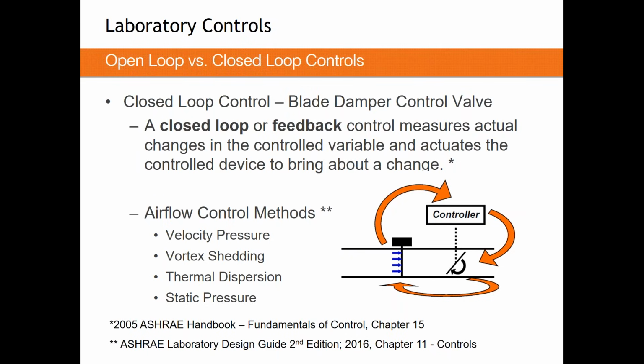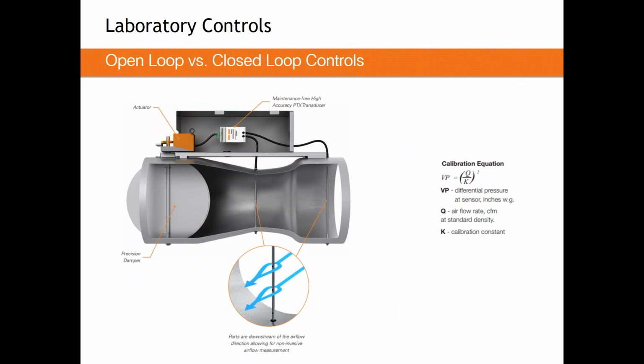The other way you can do it is measuring static pressure. I'll show an image of that because that's what we do inside our VFX as well. So those pressure ports you see in the airstream are actually measuring static pressure. Again, static pressure is directly related to airflow. You can see the equation we use on the right there. It's a very common one used for measuring and calculating airflow. Whereas if you measure the pressure and you know the constant for the valve, which is just a tested variable, you can calculate the airflow. Or vice versa. If you know the airflow and you know the constant, you can back calculate the pressure across the device.